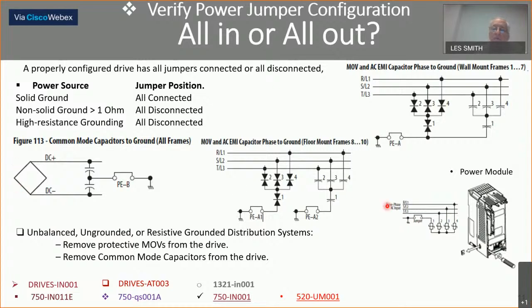On the bigger drives, frame 8 through 10, they have a little different jumper wiring here. They have PEA1 and PEA2. Now, I've thrown the 520 in here. It has a separate jumper here, placed thusly. You put the screwdriver behind the plastic, go down, loosen up the drive, pull out this little horseshoe-like jumper, and then tighten the screw back up.